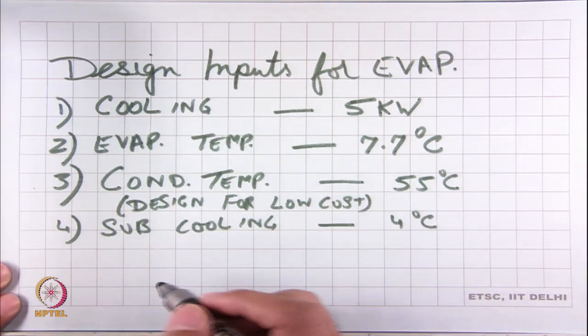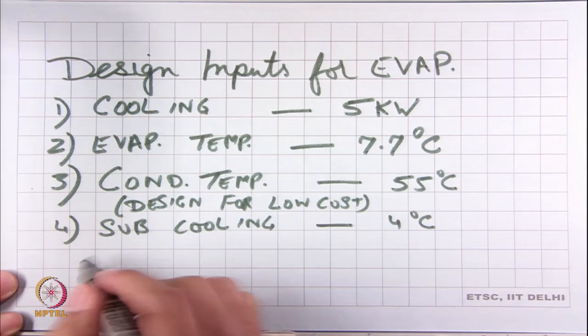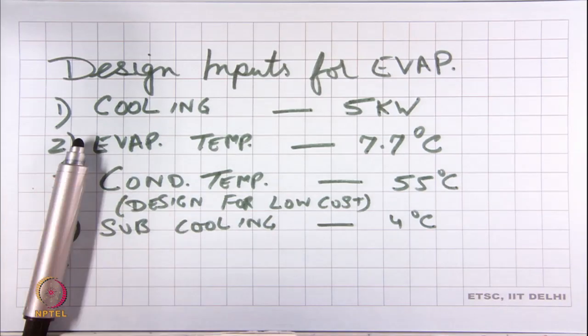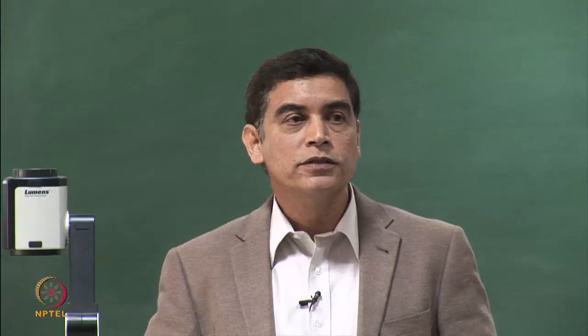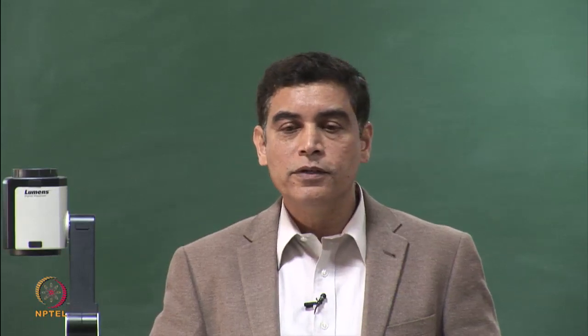With these assumptions, we have enough to choose the expansion valve and come to an evaporator design where we would have an entering refrigerant condition at state point 4. We will have an entering air temperature as a combination of dry bulb and wet bulb corresponding to the temperature we want to maintain. If we are being precise, we could add a 2-degree temperature rise in the ducts.